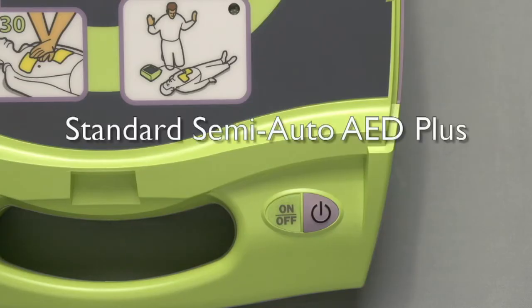The same graphic icons recall the rescuer's training and show them what to do, along with the same display screen and voice prompts. [Device]: Push harder. The difference becomes obvious immediately after you turn it on. [Device]: Automatic defibrillator. Unit OK. Adult pads. Some of the labeling on the fully automatic AED Plus also differs from the standard semi-automatic model.